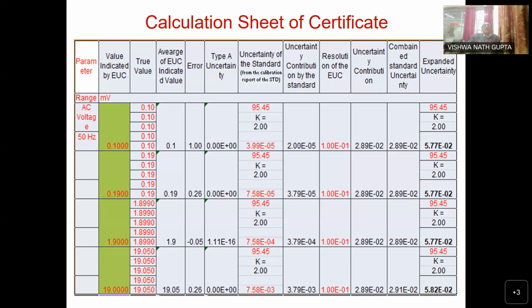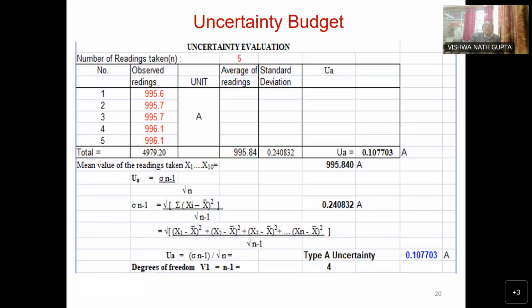Then type A uncertainty. Sir, this uncertainty is also a very big chapter; the full international community has evolved certain procedures to calculate uncertainty. If we see the uncertainty budget here, uncertainty consists of two types of error: one is random error, one is systematic error. Once we take the reading, the observed reading 995.6, it may be 995.7, it may be like that if you take 5 readings. So we take the mean value, which is called the average reading. The formula for standard deviation is there, sir. These are big chapters; this is for illustration only.